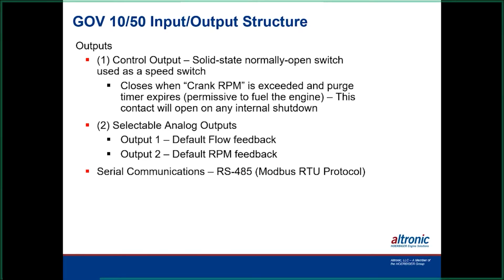And then we have two outputs on it. One can be calibrated for the fuel flow, it's a 4 to 20. And then one can be calibrated with a 4 to 20 for the RPM. And then all the other data can be brought in on the serial communication with the RS-485.